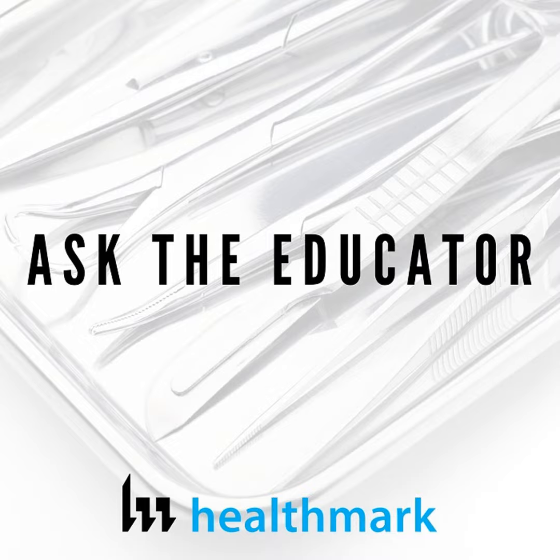It's a great question. With the cleaning process, especially with any mechanical cleaning equipment, there are multiple factors at play to produce a clean instrument. With ultrasonic cleaners specifically, the components that produce lumen cleaning or flushing come from separate equipment within the ultrasonic. It has its own pump, its own tubing, its own filter system, and all these components, even the hookups and O-rings, could possibly go wrong.